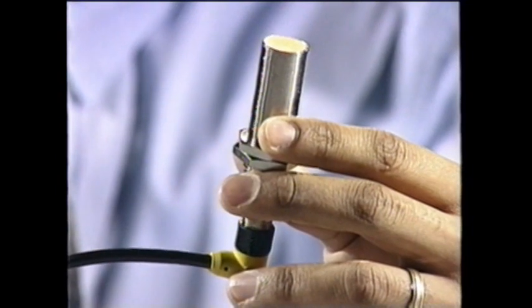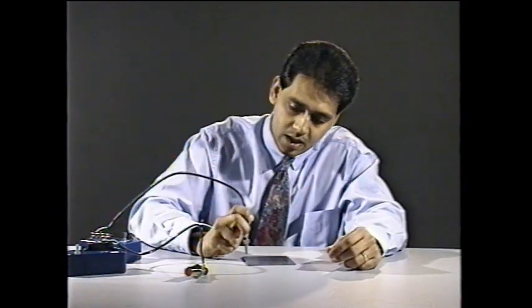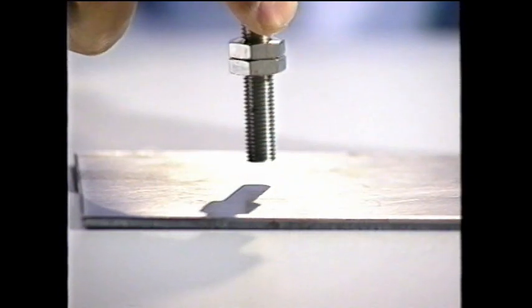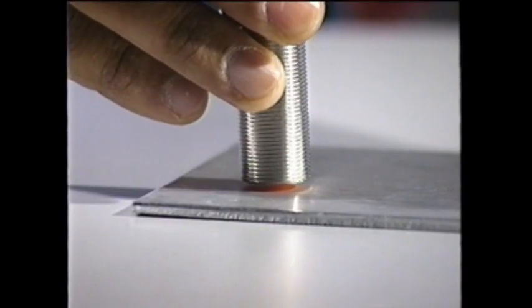I have two proximity switches here. Both are wired to DC power supplies to illustrate this point. One is an 18-millimeter switch, and the other is an 8-millimeter diameter switch. The 8-millimeter inductive proximity switch has a smaller ferrite core than the 18-millimeter. Therefore, it has a smaller sensing range. You can see the sensing range is approximately one millimeter. The 18-millimeter switch has a larger ferrite core and has considerably more sensing range — approximately five millimeters. Therefore, the larger the ferrite core, the more sensing range you would have for an application.